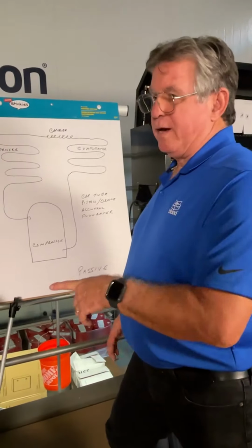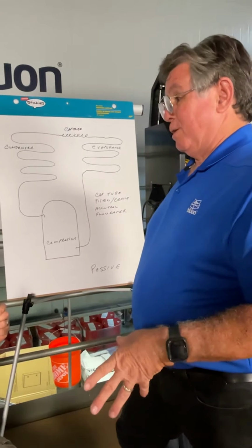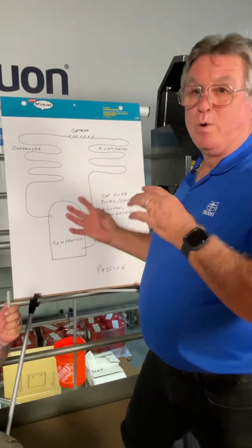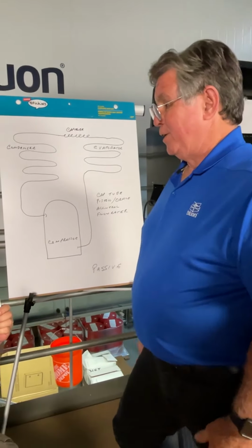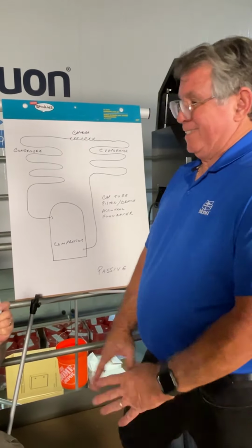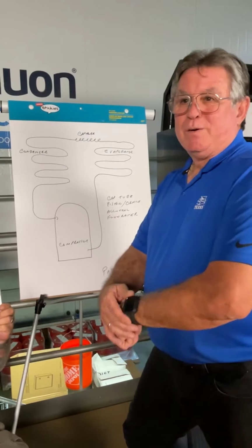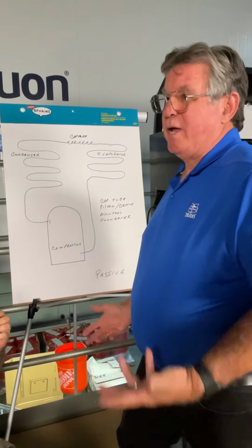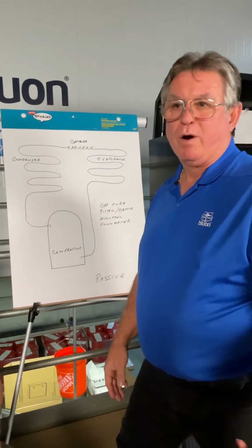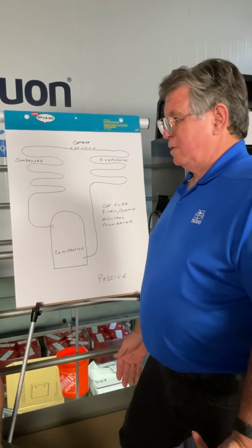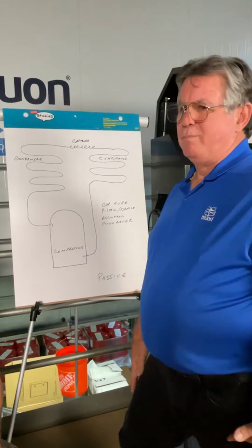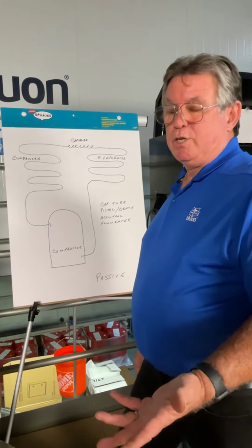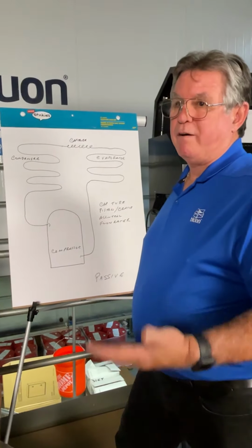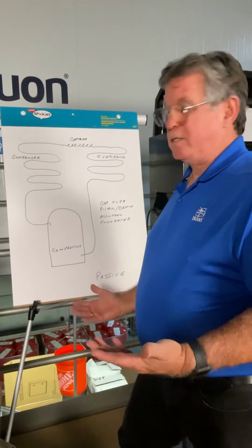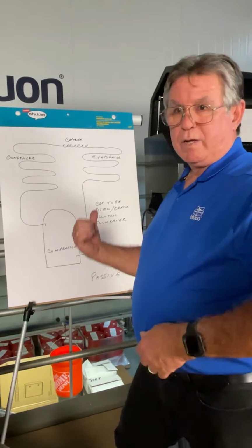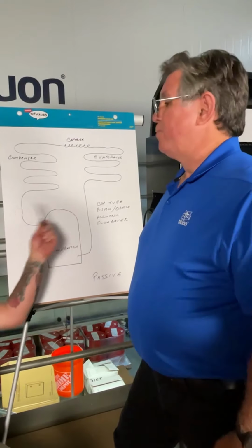And I'm glad you brought that up, because many years ago, when I would talk to people, because I came from a world where cap tubes were non-existent. You don't use them on 2,000-ton systems. They're not there. So everything with me was expansion valves. And so when I come back, I said, so what target superheat do you go for? And everybody says, well, 12. And I'm like, oh, wow, okay. And I started looking at it, and I'm like, no, that ain't right. Your superheats can go anywhere between about 5 and 50 degrees of superheat on a small system, depending upon those 2 points.